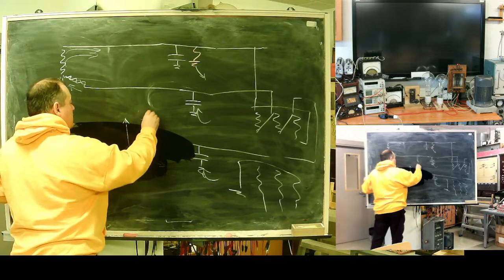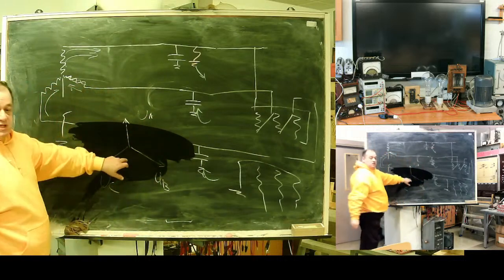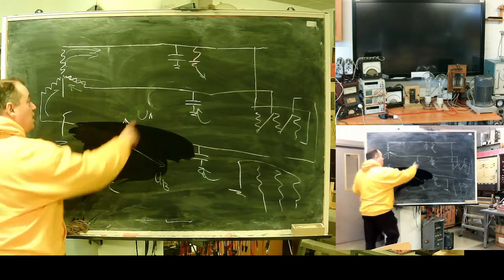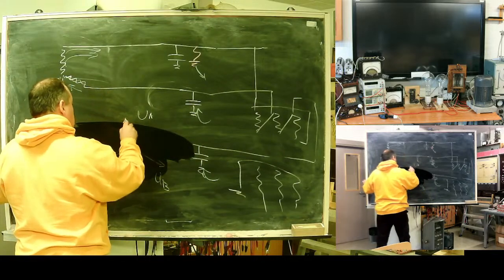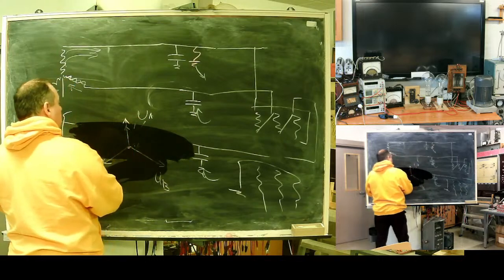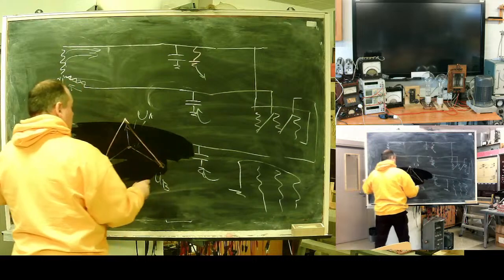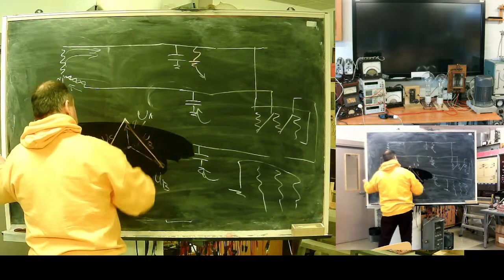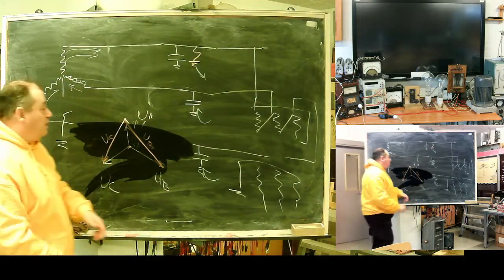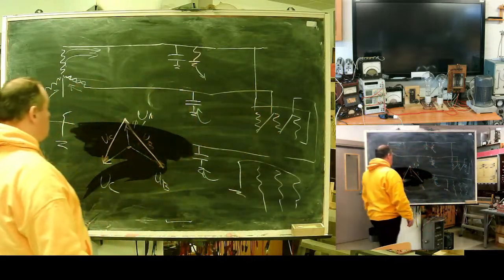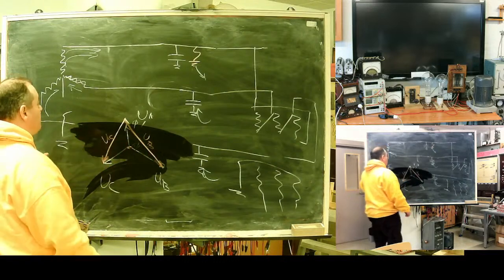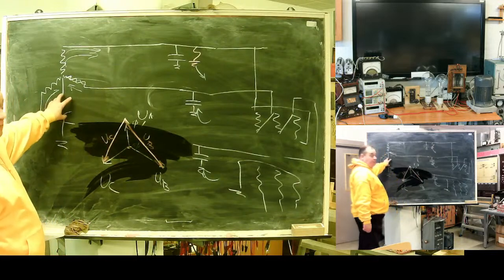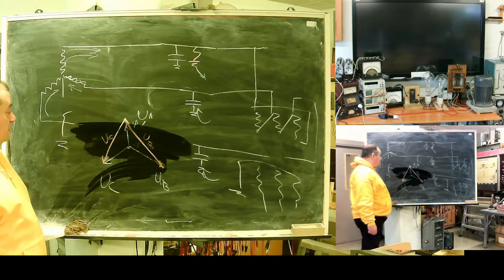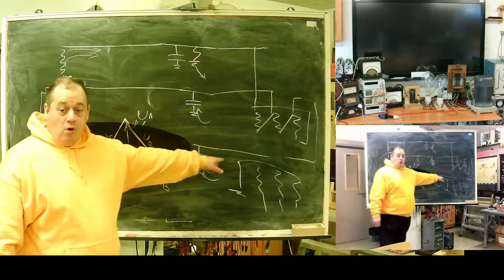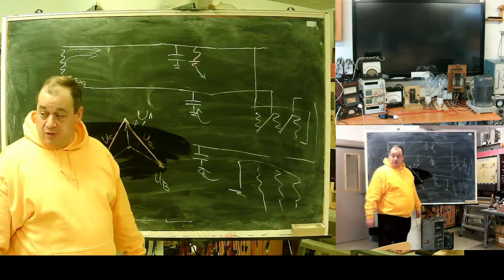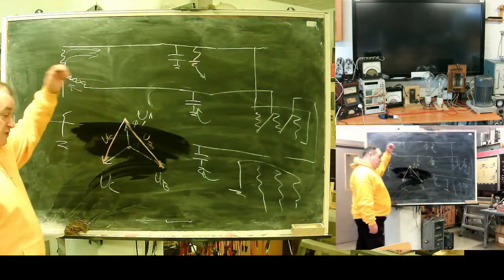If, let's say, A, B, C, this was the voltage star against ground before the fault, I have this value. So the zero point will shift. This will be B voltage and this will be C voltage. It's again ground. But we have delta here. Line voltage does not change. The neutral point, the zero point, if we plug a voltmeter here, it will show us the shift. But line voltage does not change, so the load continues operation without any disturbance.